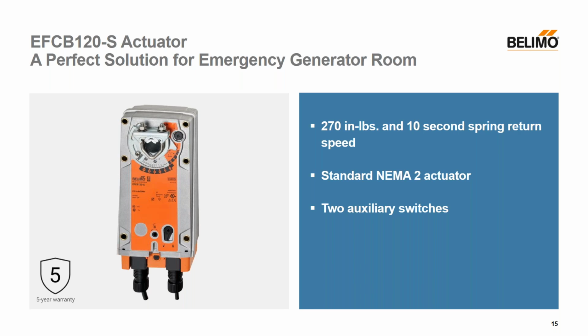2 actuators can be dual mounted, wired in parallel for more torque to the same shaft. Comes standard with 2 auxiliary switches, and it's a perfect solution for critical applications where maximum airflow must be achieved quickly, such as emergency generator combustion inlet dampers. And this can be found on page 2-1 in the 2022 PGPL.